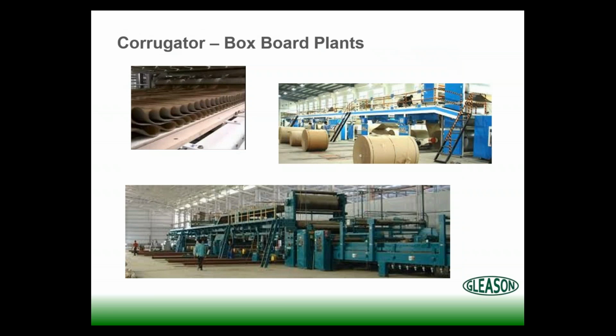Corrugators. 92% of all products in North America are shipped in what? Cardboard boxes. So corrugators typically produce steam at about 220 psi, and many of them are returning under pressure at about 120 psi. And they do that because it's such a competitive, cutthroat industry. They have to do that to get all that BTU value and that very, very hot water back to the boiler, so they're burning less fuel to bring that very hot water back up to steam temperature.